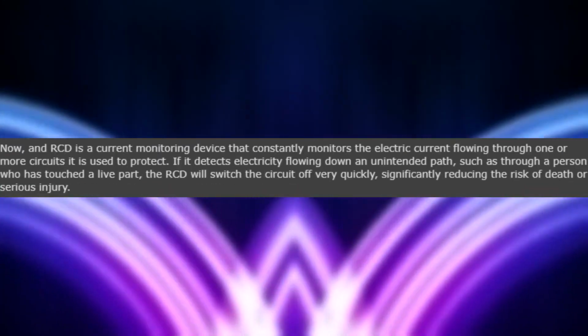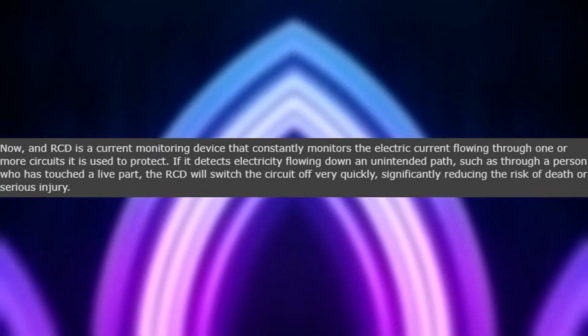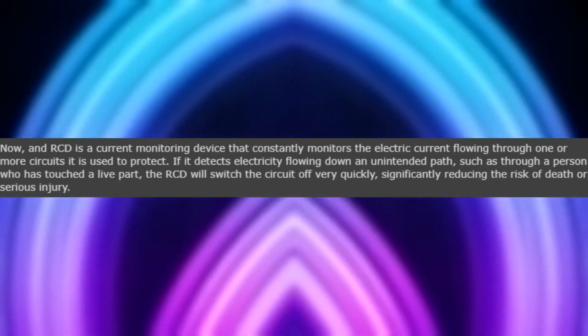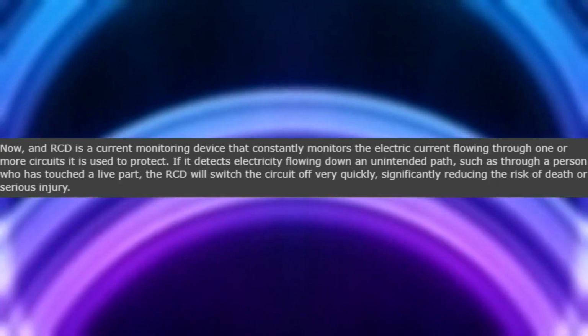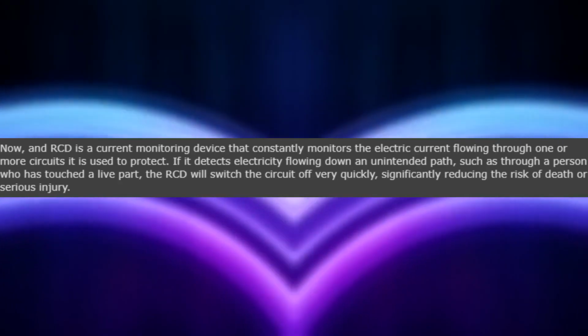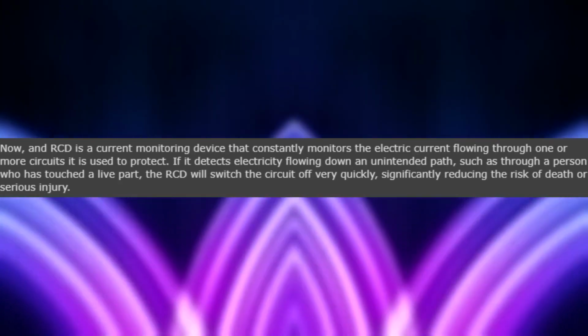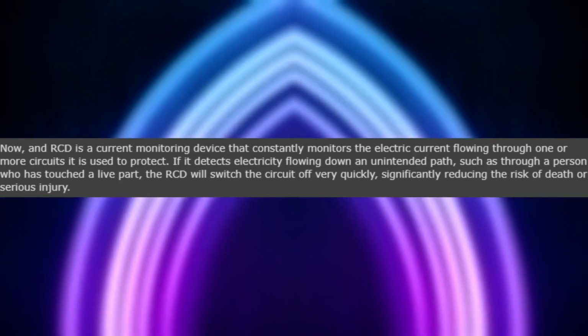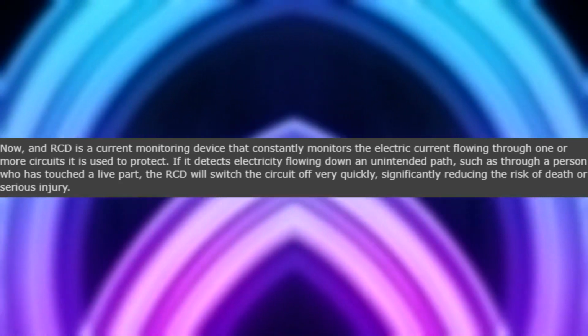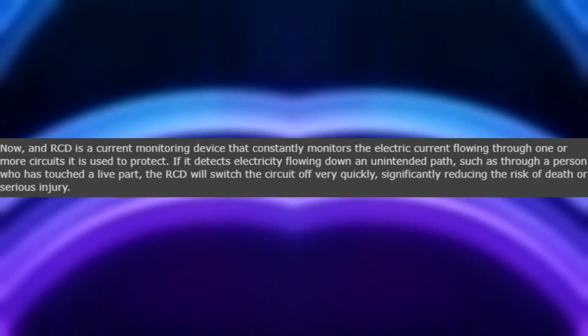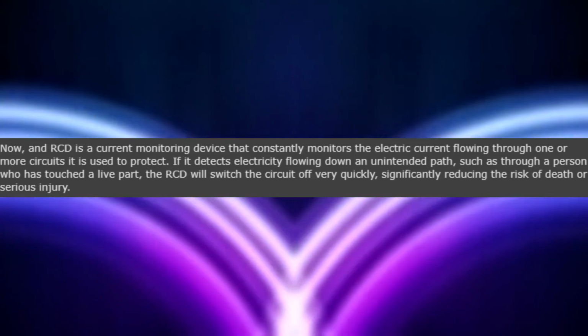Now, an RCD is a current monitoring device that constantly monitors the electric current flowing through one or more circuits it is used to protect. If it detects electricity flowing down an unintended path, such as through a person who has touched a live part, the RCD will switch the circuit off very quickly, significantly reducing the risk of death or serious injury.